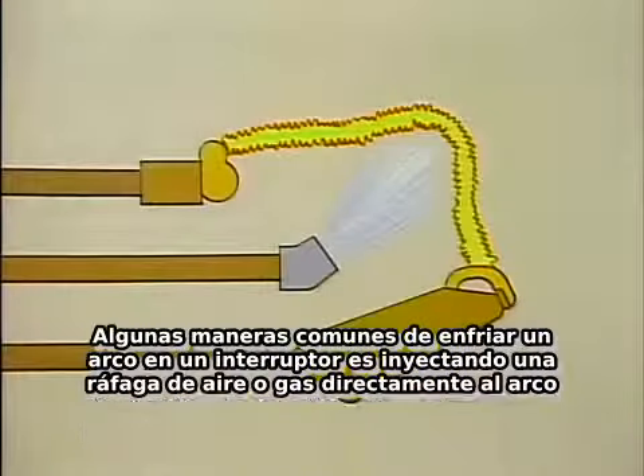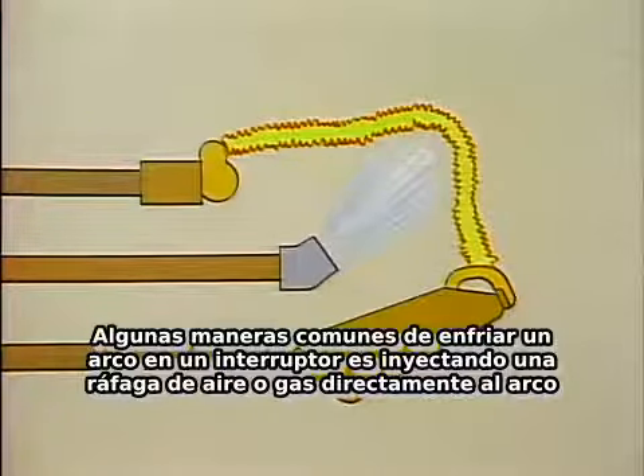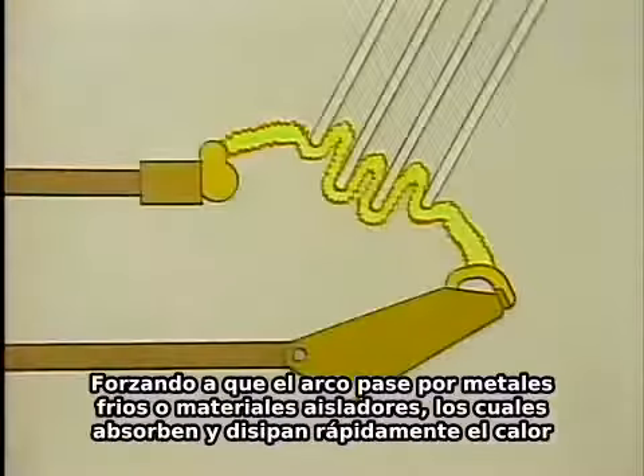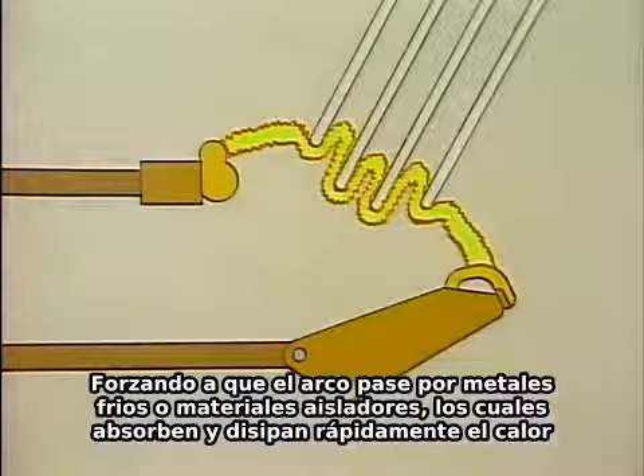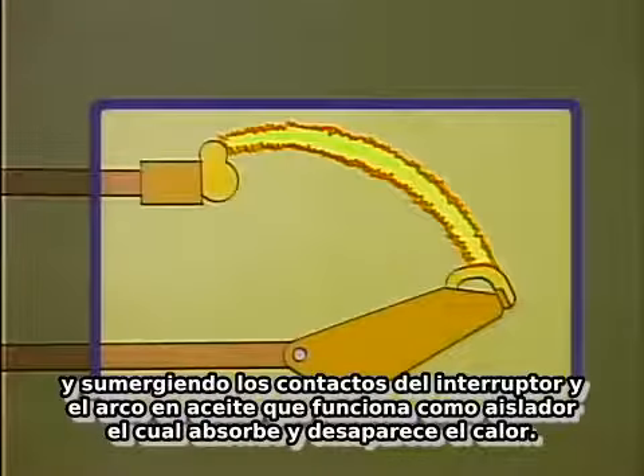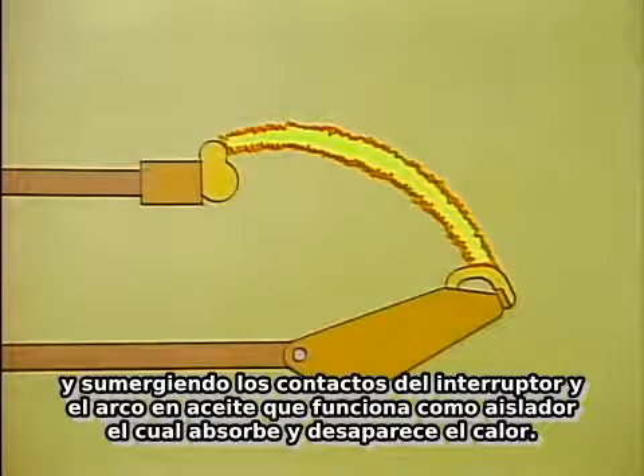Some common ways that an arc is cooled in a breaker include directing a blast of air or gas at the arc, forcing the arc against cold metal or insulating materials which rapidly absorb and dissipate heat, and submerging the breaker contacts and the arc in insulating oil which absorbs and dissipates the heat.